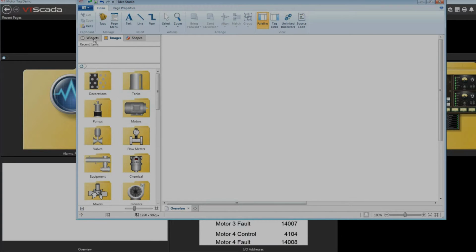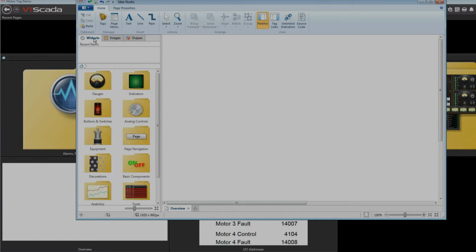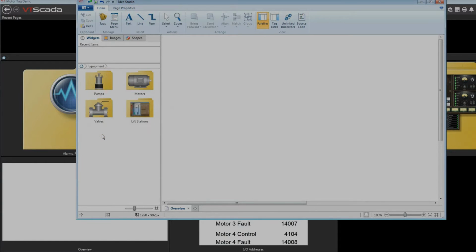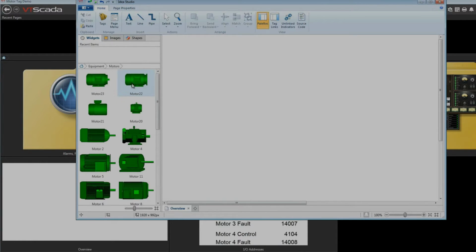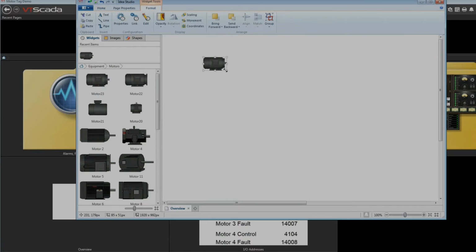So in order to come up with something that's going to be animated on the screen so the operator can actually see the status of the motor, I'm very, very careful to make certain that my selection is with the widgets palette. Now I'm going to be able to go down to my equipment images, or widgets, and from there I can find that I've got a group of motors. I'll take one of these motors, drag it onto the screen, and if I wanted to, I could grab one of these grips to resize it, make it larger, smaller, as required. At this point, you notice that it's blinking green and gray.